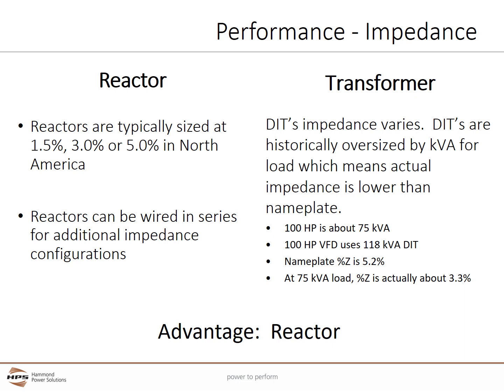DITs are historically oversized by kVA for the load, which means the actual impedance is lower than the nameplate. Here's an example. A 100 horsepower motor is about 75 kVA. A 100 horsepower VFD uses a 118 kVA DIT, even though the load is only about 75 kVA. The nameplate, or percent Z, of the 118 kVA in this example is 5.2%. At 75 kVA load, the percent Z or impedance is actually 3.3%. If the user wants 5%, a custom DIT may need to be sourced. Due to ease of selection, flexibility, and availability, reactors provide better impedance performance.